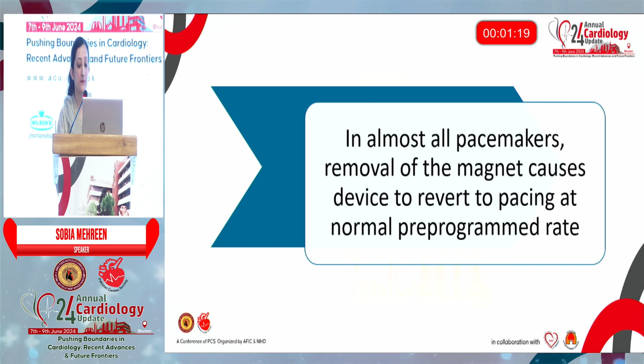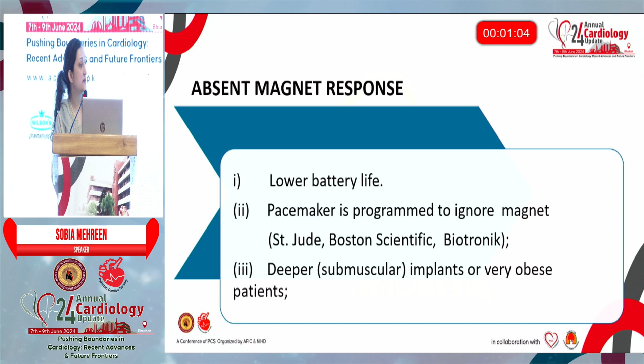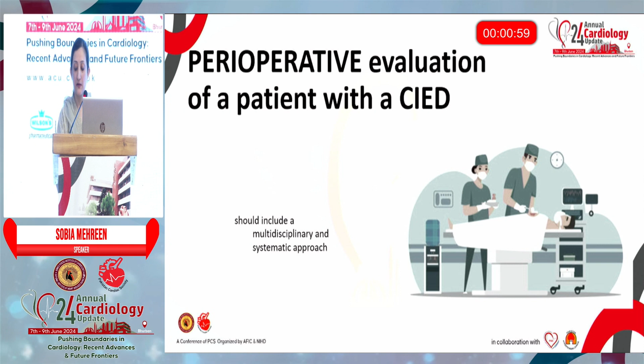However, if we place a magnet and no magnet response occurs, it can mean that the battery life is low, the pacemaker is programmed to ignore the magnet, or the pacemaker generator is deeper inside, as in submuscular implants, or the patient is very obese so that the magnetic field does not reach the generator.